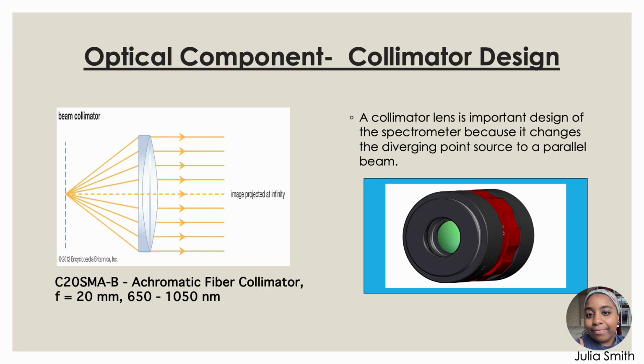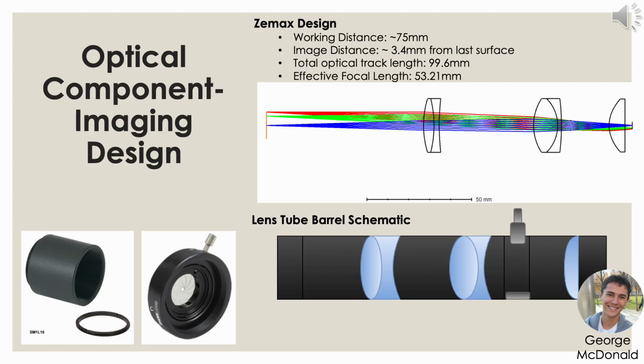The collimator lens is important to our design because it changes the diverging point source to a parallel beam. The reason we want this is to be able to capture all of the light going into the beam splitter. I found a collimator package instead of designing one, which would work for the limits of our spectrometer and has a tunable focal length. Our lens design has an overall magnification of 1/4.